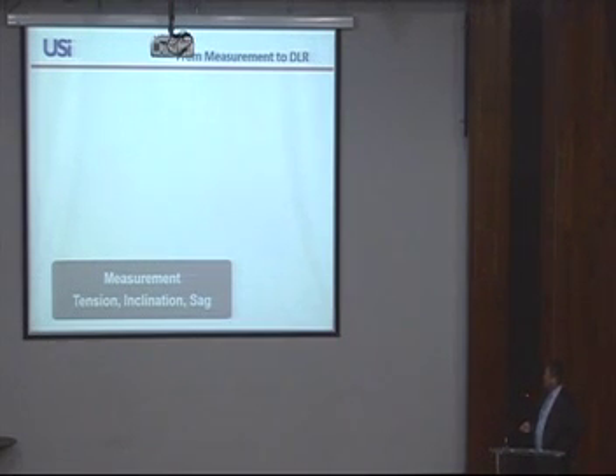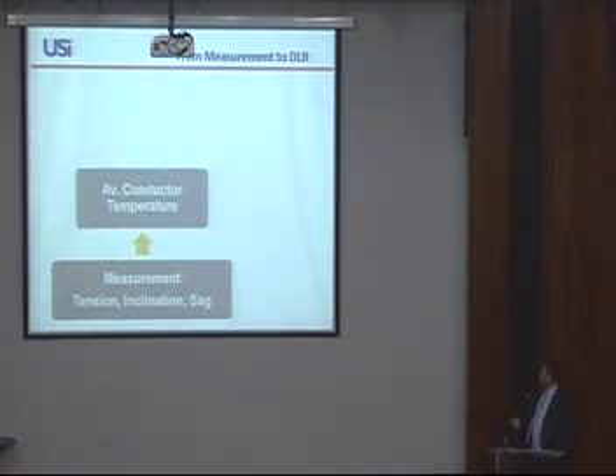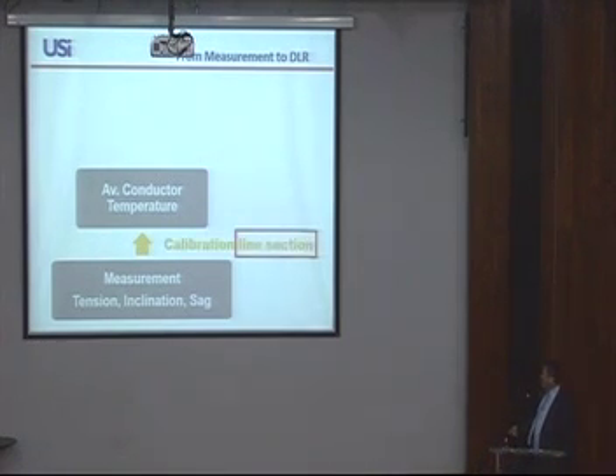So now we are at the beginning, we have the measurements: tension, inclination. Alternatively, if you have the possibility to get the sag, you cannot measure it, but if you get it from somewhere else, maybe from clearance measurements. So starting from those measurements, we can determine the average conductor temperature, and for doing that, as I mentioned earlier, you need the calibration of a line section. That means you have to find out what is the as-built condition, the relationship between the two parameters. This is done in our case by using our field measurements.